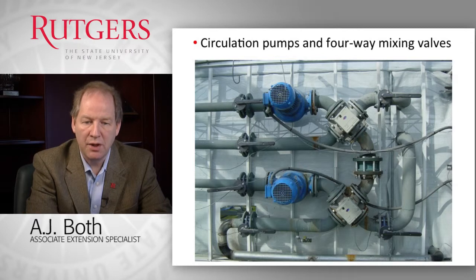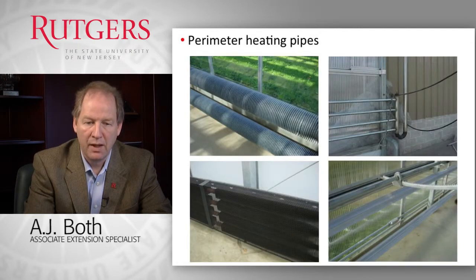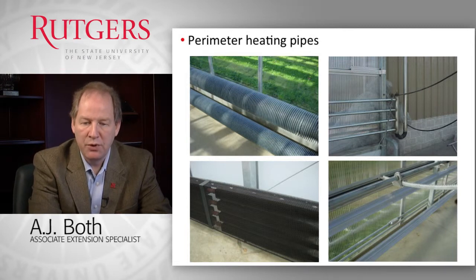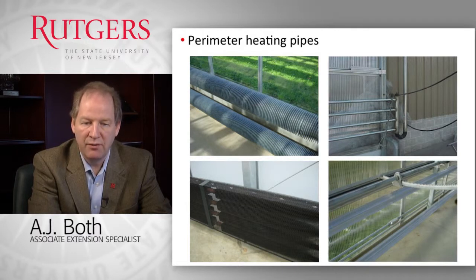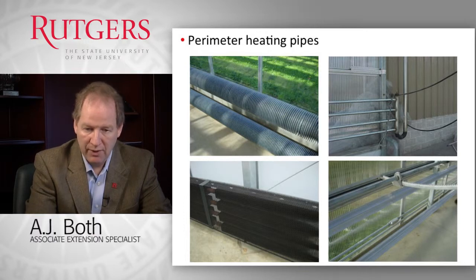Here you see an installation with four-way mixing valves and, shown in blue, the circulation pumps used for each zone to pump water around when needed. There are different designs for the heating pipes used with hot water systems — they can be smooth or equipped with fins in various designs to increase convective heat loss and ensure that energy provided as hot water is quickly and completely released into the greenhouse environment.